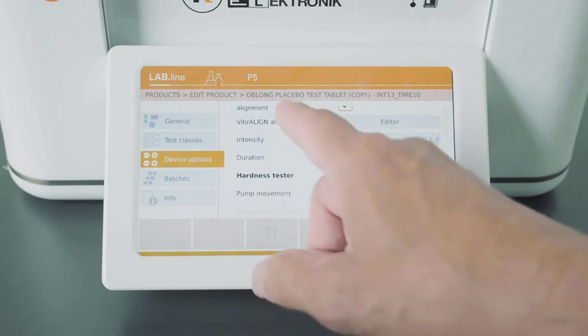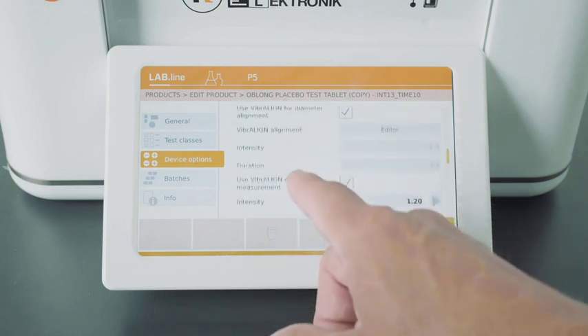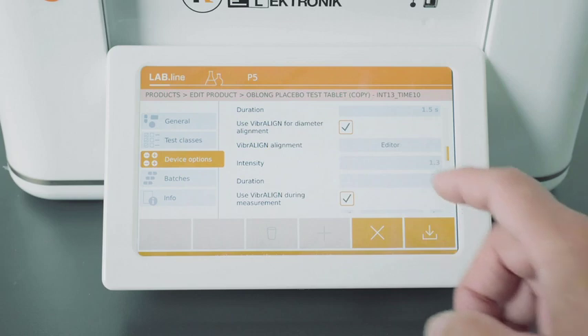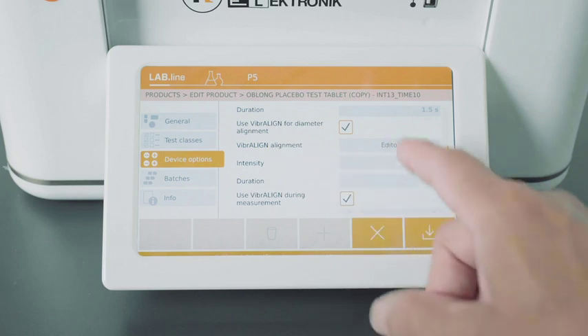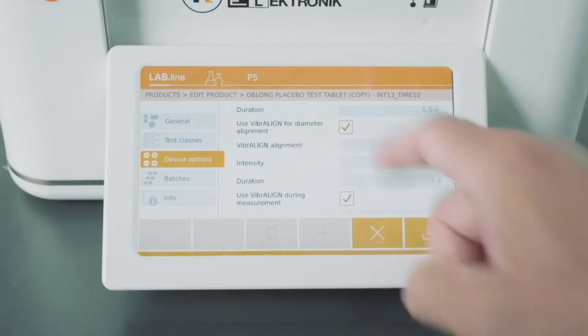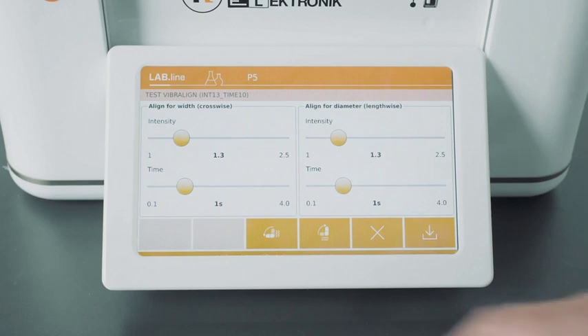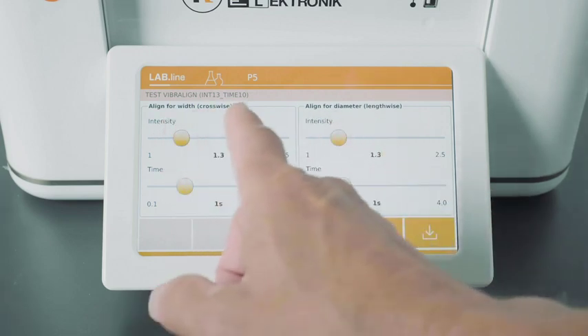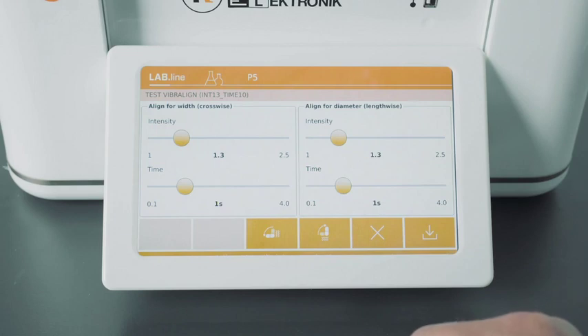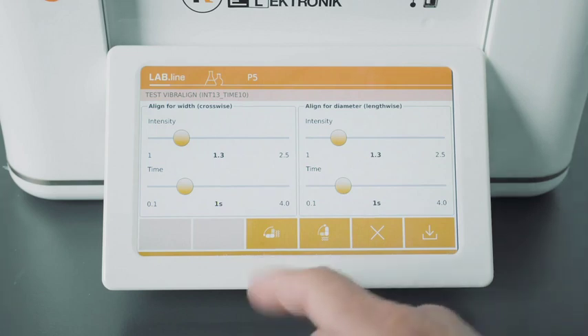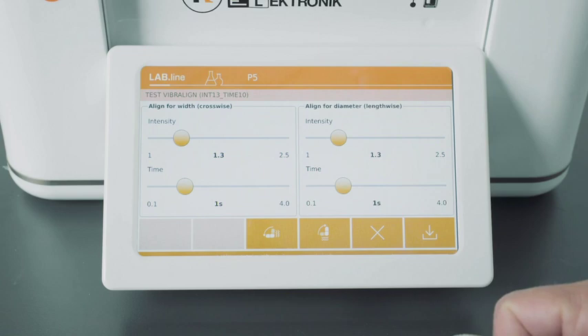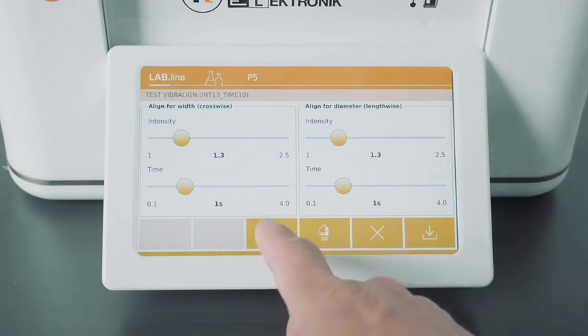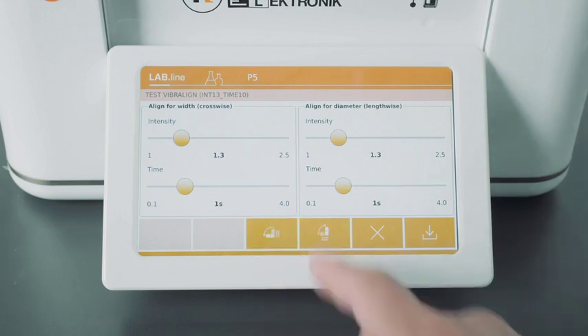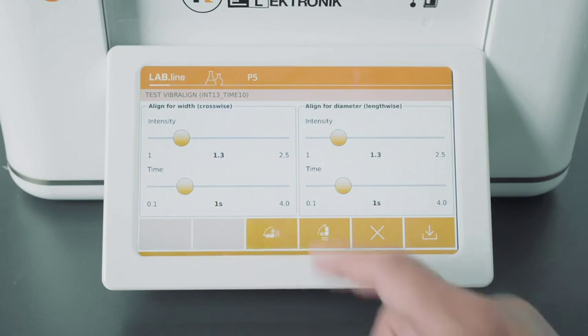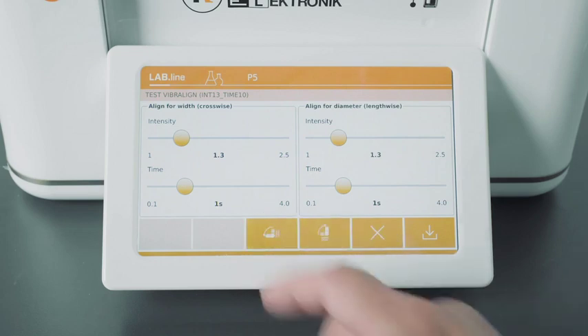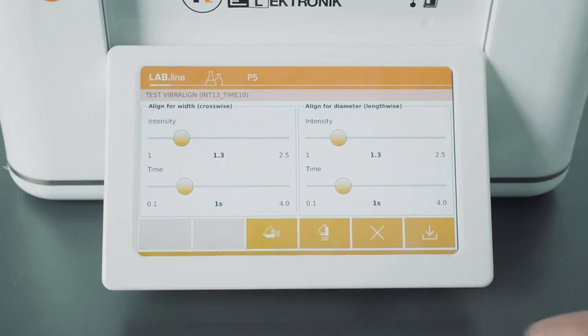Now, to find out which value to set up for the VibrALIGN intensity and duration, you have an editor here that you can change intensity and time for both, and then you can place your tablet into the hardness station, and you can use these buttons to check how the tablet moves its position from diameter measurement to width measurement.